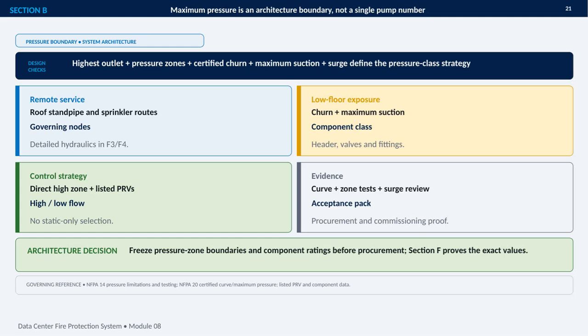This section establishes a critical design principle. Maximum pressure is an architecture boundary, not a single pump number. The governing condition is created by several factors working together, including the highest outlet, pressure zones, certified churn pressure, maximum suction pressure, and potential surge. The design checks begin with the most remote service points, particularly roof standpipe and sprinkler routes. We identify governing nodes, then verify the detailed hydraulics in sections F3 and F4.